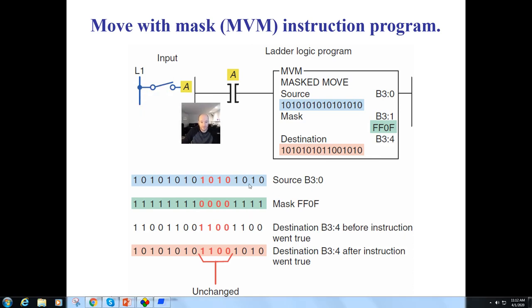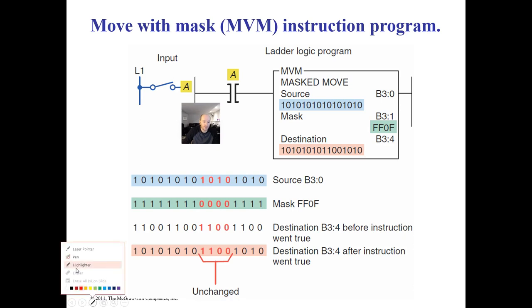And this is how it works. Basically, here's your B3. You have a bunch of inputs in there. Then you have a masked word. And this is being represented in a hexadecimal number. So four ones, four zeros, and the rest are ones. So basically, anywhere you have a one in your mask, that data will be transferred down. So if I have a zero here, it will filter down. I have a one here, so this one will get transferred down. This is what it was before it went true. This is what it is now that it does go true.